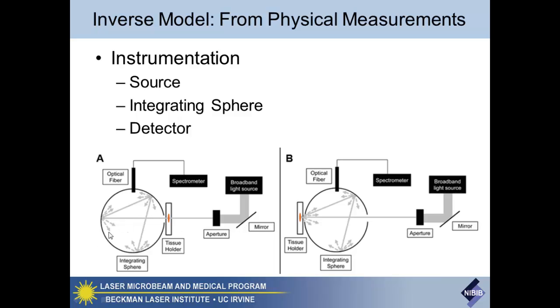enters this integrating sphere. The integrating sphere basically says that if you shine a narrow beam of light, a collimated beam, through your sample from the transmitted side, even though light will be scattered when it interacts with that slab, putting it in close proximity to the entrance of the sphere means it will collect all the light scattered at all angles from that sample, allow it to bounce around within that sphere, and you sample a small portion of that, which is now all evenly mixed. So again, all angles of light, and it is sent to a spectrometer and detected that way.